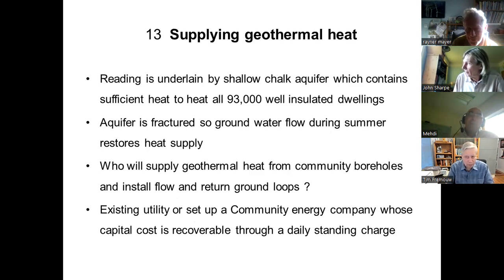Rainer, I'm not sure about that, because you may get to the water resources when you are digging 70, 100 meters deep, and always for going for borehole and ground source heat pump technology, it's advised to consult with the local authority for the appropriate permissions. It would be much more appropriate in the first instance to consult with BGS, because depending on where you are, you can then inform the planning authority. But as far as I know, there's no planning requirement, provided you do it on your own property and it's a sealed borehole system. If you've got an open loop system, it's slightly different.